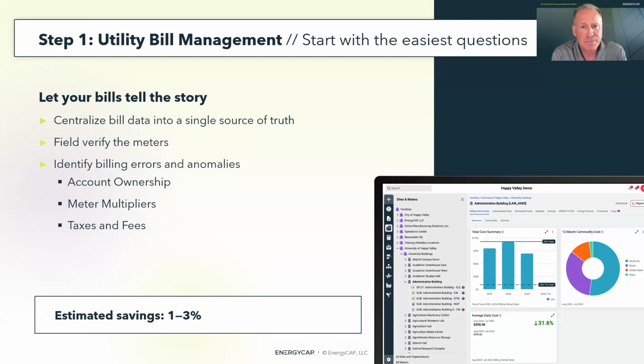But if you have a massive building, let's just say a high school that we've all had experience with, something that might be 100,000, 500,000 square feet, just huge buildings. Usually those have meter multipliers of 500 or 1,000. They're very, very large. So the main thing is there's nothing broken about having a multiplier. What's broken is if the multiplier doesn't match the bill. That's when there's an opportunity to save and catch up with the utility company because they might be taking more of your money than they deserve.